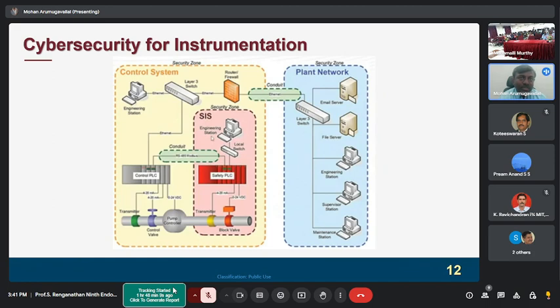And nowadays the cybersecurity standards mandate that there is no direct connection between ESD and the DCS. So you need to have a firewall if you want to connect these two devices. So different zones communicate through conduits. These conduits are tightly tuned to enable communication between the zones only during special identified nodes only. Not every node can access the other node in another zone. So these are the conduits.